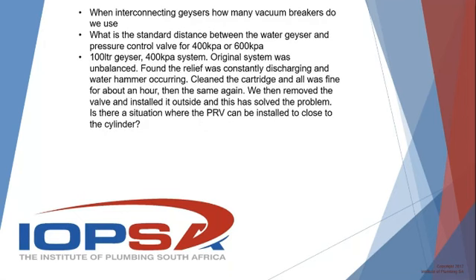Yeah, 100%. I've spoken to manufacturers on that. Maybe I can come in and just add there. The Cobra master flow valve, for instance, is very specific. As Patrick said, on 100 kPa it is within 1 meter of the geyser. 200 kPa, which is rarely used, is 2 meters from the geyser. And on the 400 kPa it is 10 meters. So that is where this 10 meter argument comes in a lot. That manufacturer specifically has a 10 meter on their 400 kPa, and they don't have a 600 kPa.